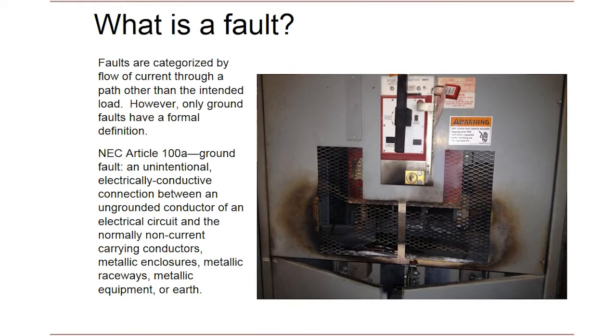In contrast, a fault is where current flows through a path other than the intended load. The NEC doesn't formally define a fault — they only define a ground fault. But line-to-ground faults aren't the only potential fault mode. There are also line-to-neutral faults where the current short circuits the load and goes directly back to the source, and line-to-line faults where multiple phase conductors come into contact with each other, forming an unintended conductive path.